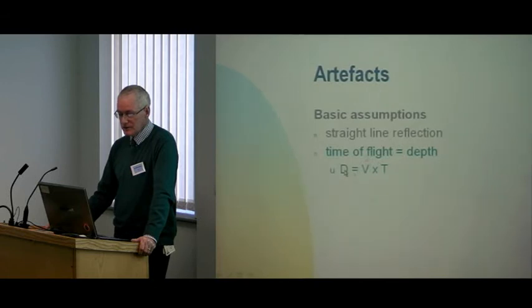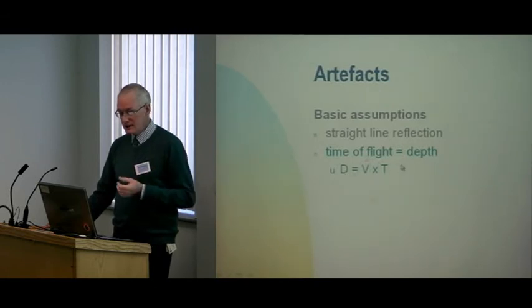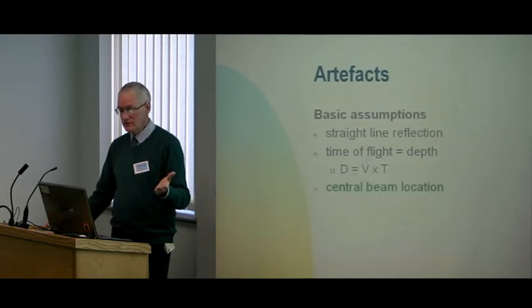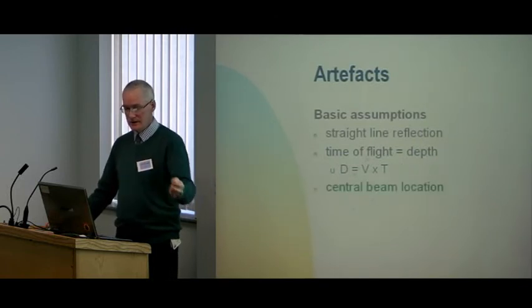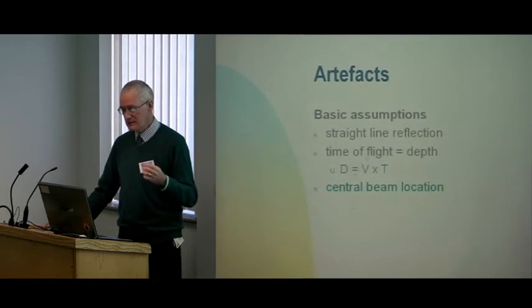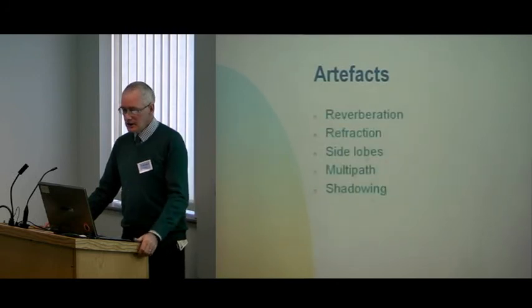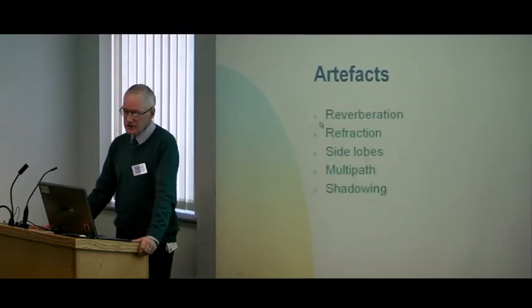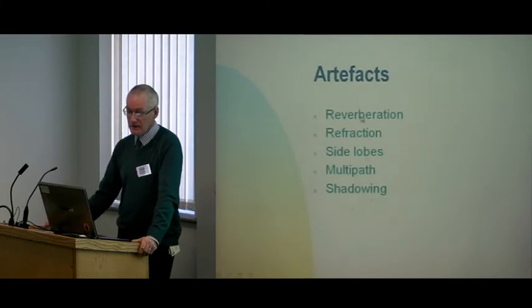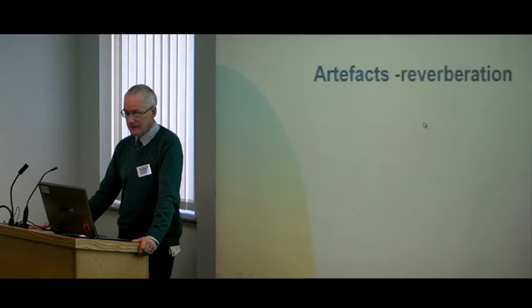The actual dot is produced at a certain depth according to how long it takes for the reflected sound to arrive. All machines will presume that it takes a certain time to be reflected back, and the image will be plotted according to the time that's taken to reflect back. Because of those assumptions, the machine will produce some artifacts that you'll need to be aware of in order to prevent you misdiagnosing.